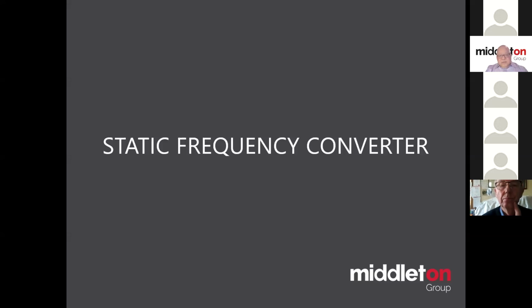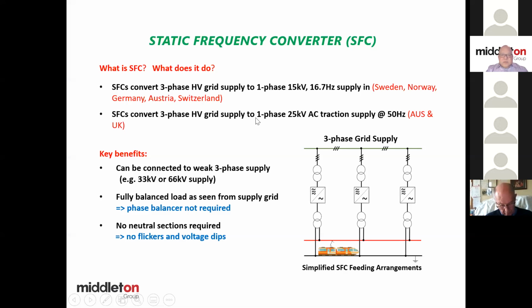Now, this is a relatively new system. Why do we use a static frequency converter? It has been used for a long time in the continental European countries, Sweden, Norway, Germany, Austria, and Switzerland. They used it to convert the HV supply grid system, some 110 kV, some 132 kV, and 50 hertz, to 15 kV and 16 2/3, 16.7 hertz to feed the railway. So they use one third of the frequency that we use in Australia and the UK. In the UK and Australia, we don't change the frequency at all. It stays at 50 hertz. We're only using it to convert from 3-phase to 1-phase.